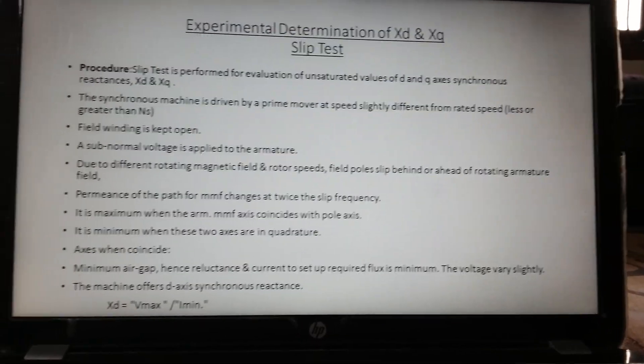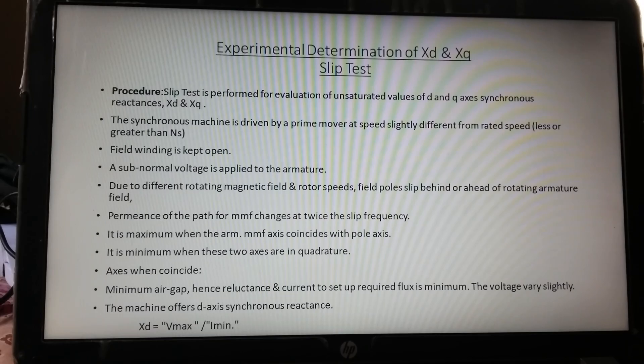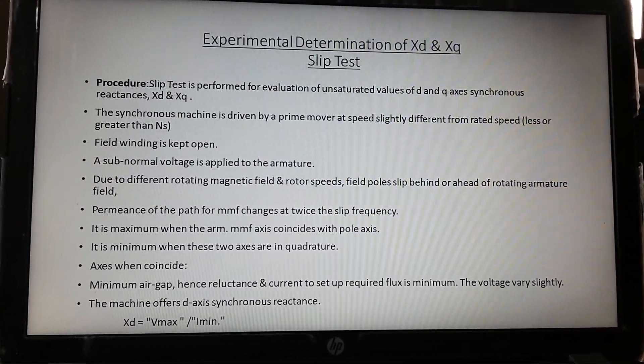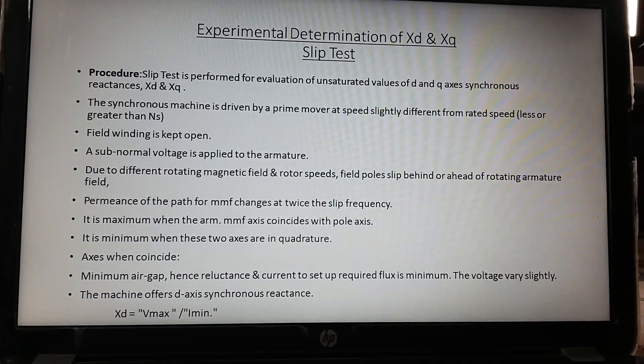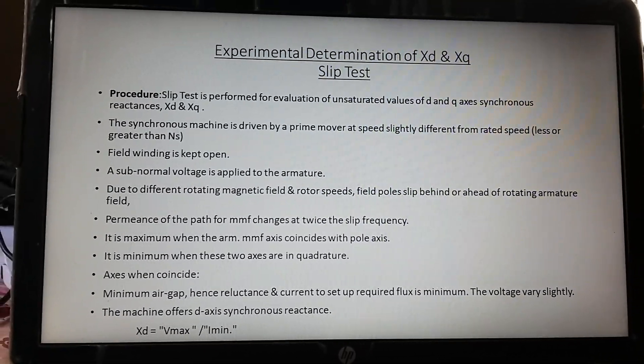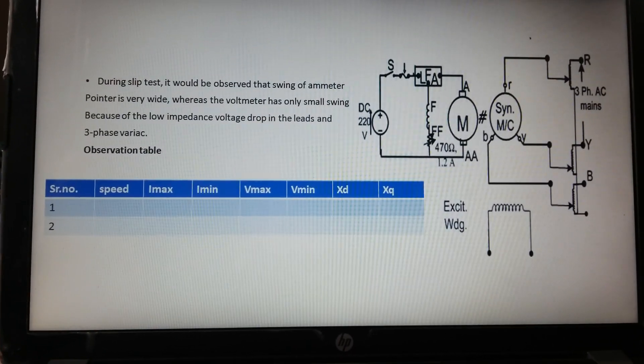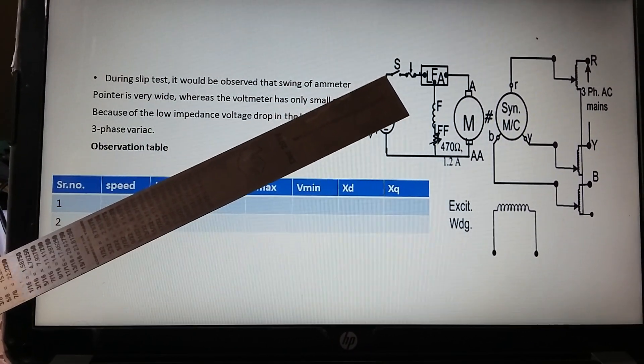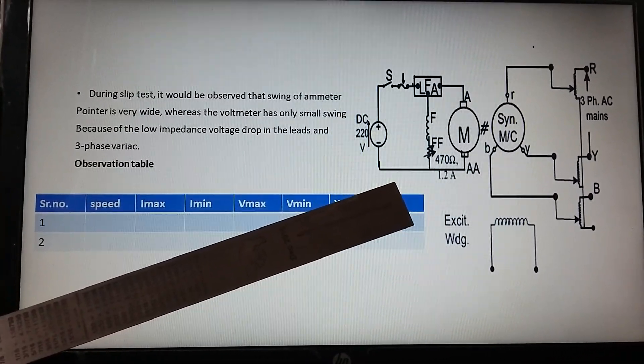The topic is the slip test. The purpose of this slip test is to identify or determine Xd and Xq, that is the synchronous reactance of a salient pole machine. When d and q axes are coming, that means the machine is a salient pole machine. Let us understand how this test is performed and how these parameters are identified with the help of the lab setup. Slip means we have to maintain relative velocity between field winding and armature winding, the two parts of a synchronous machine. Field winding velocity will be controlled by a DC motor.